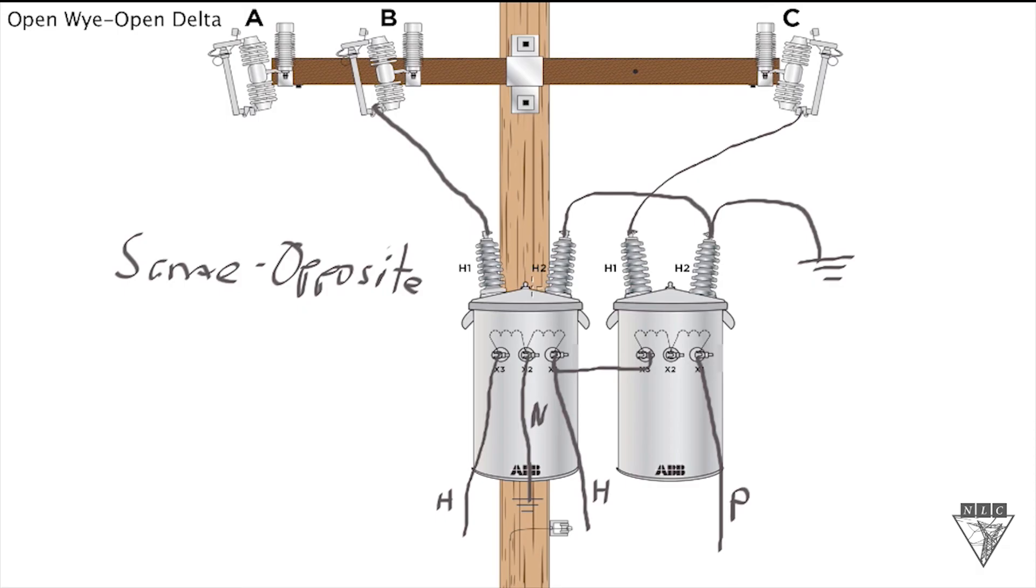Your primary side is the same—you're using the H2s connected together, those are the same. Your secondary side is opposite because you've taken an X1 and connected to an X3. It's called the same opposite connection. All right guys, that's it for this open Y open delta bank with the same opposite connection.